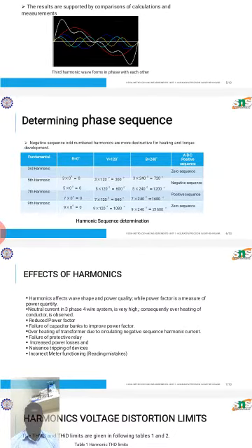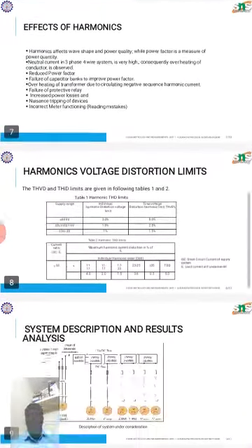Another effect of harmonic currents is the overheating of neutral wires in Y-connected circuits. This effect occurs because the third harmonic, 180 Hz, and any multiples thereof do not cancel in the neutral as the other effects do.